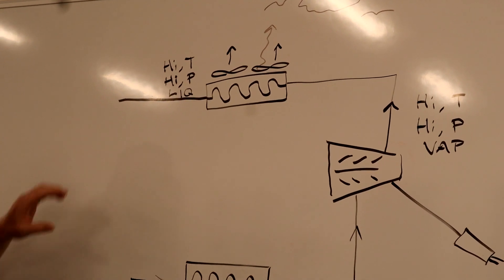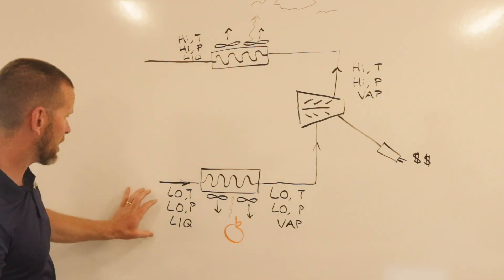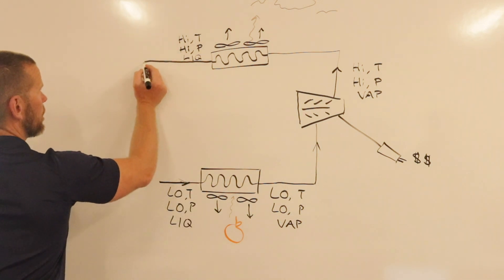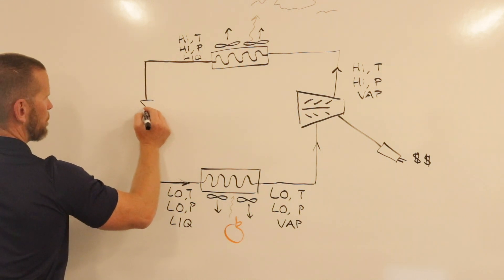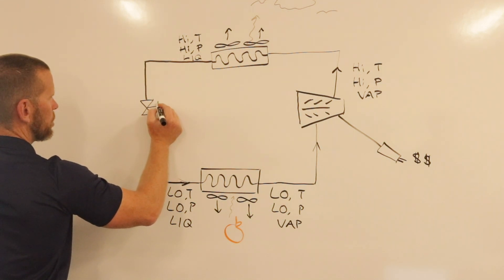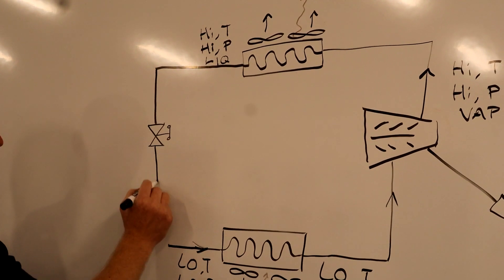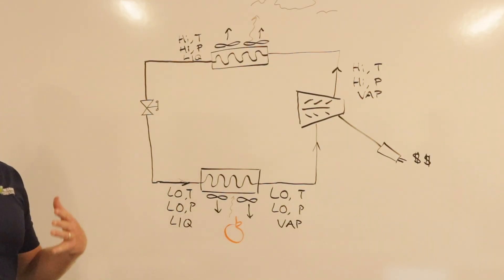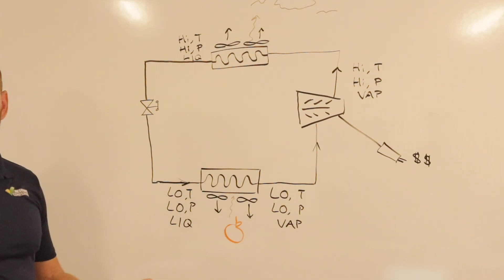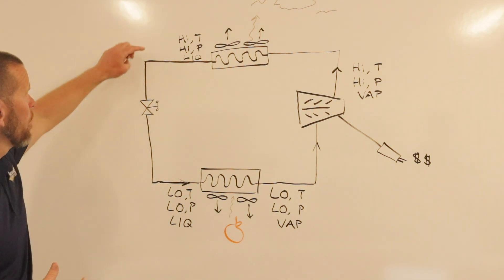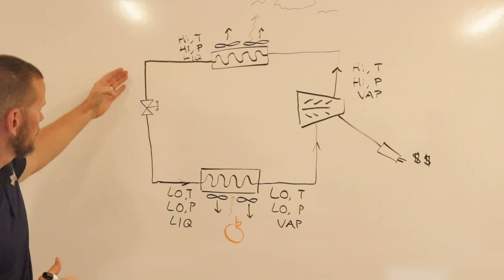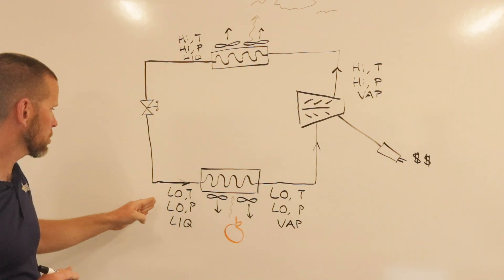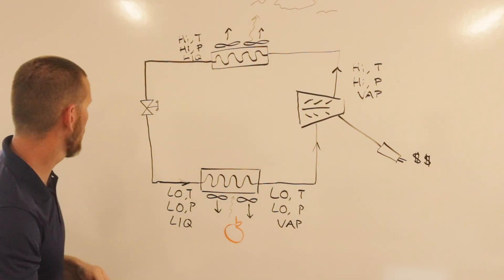To get our high temperature, high pressure liquid back to a low temperature, low pressure liquid that we need to enter the evaporator, we add an expansion device. I'll draw it as a valve, which is what you often see in refrigeration applications, though there are different types. What does this expansion device do? It's an obstruction in the piping that throttles the flow as it passes through, causing the pressure to drop. Because pressure and temperature are related, as pressure drops, so does temperature. When we pass through the expansion valve, we drop back to our original starting point as low temperature, low pressure liquid. We've drawn our cycle.